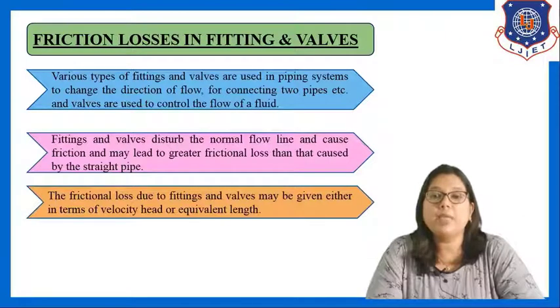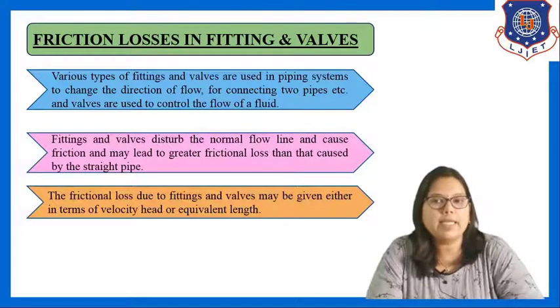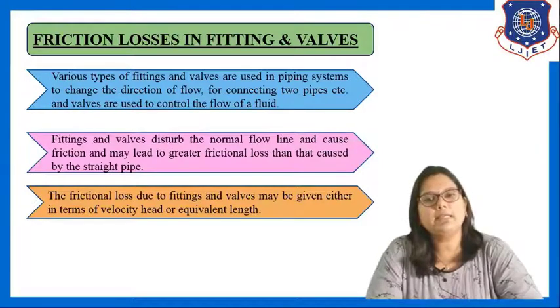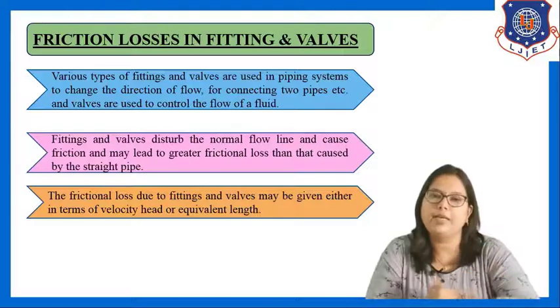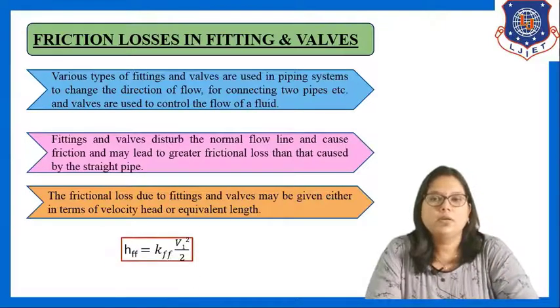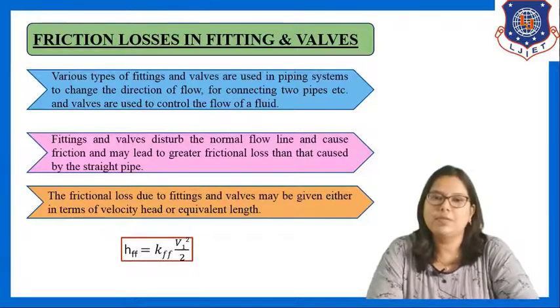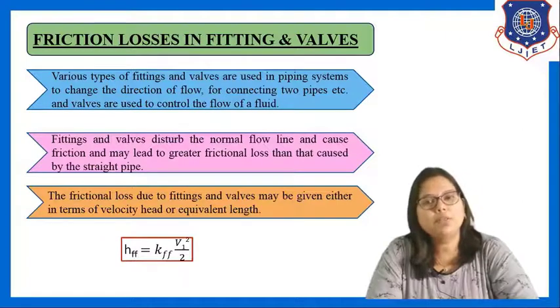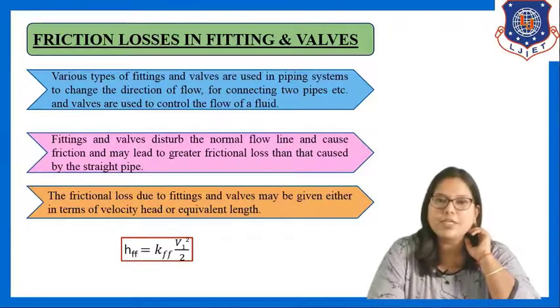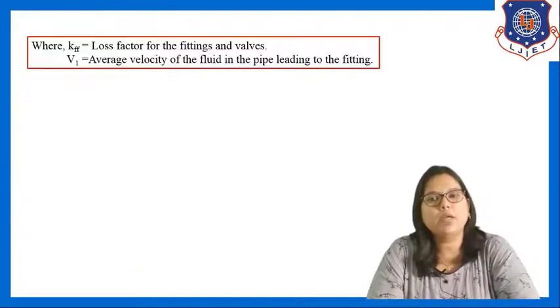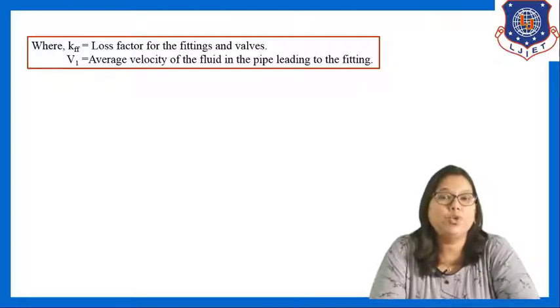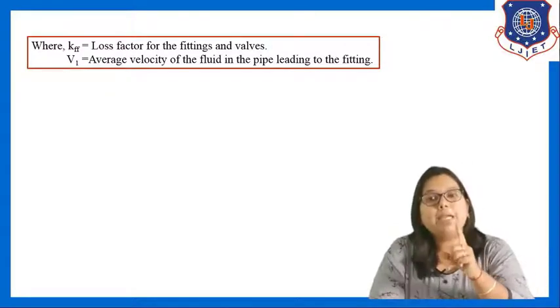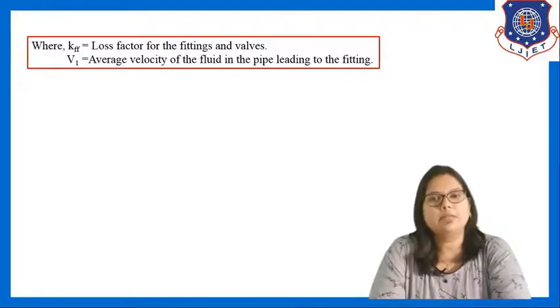The friction losses due to fittings and valves may be expressed either in terms of velocity head or in terms of equivalent length. HFF, which is the friction loss due to fittings and valves, is equal to KFF·V1²/2. This equation is similar to sudden expansion and contraction. KFF is the loss factor for fittings and valves, and V1 is the average velocity of the fluid in the pipe leading to the fitting.